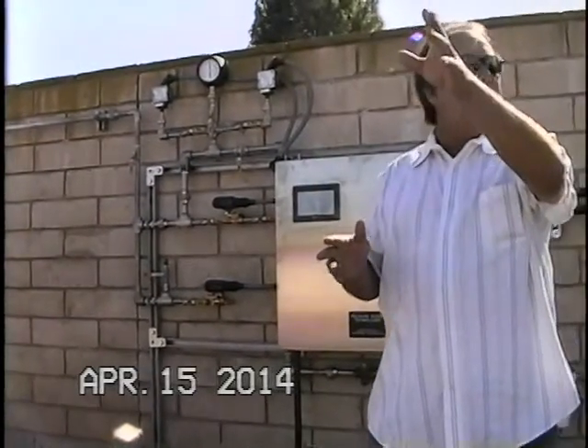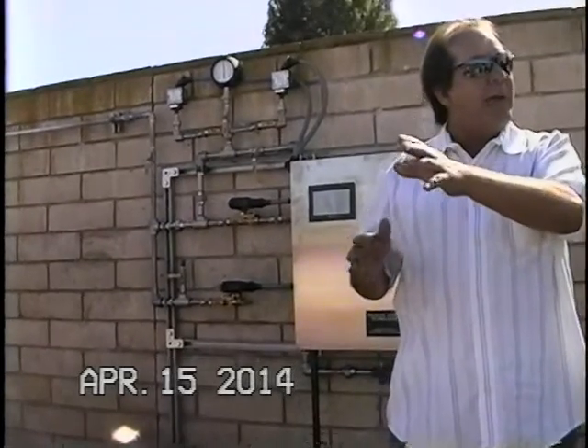In a surge tank, when the pump shuts off, we've got effluent flow, all this water leaving the pump station. Because of the velocity in the pipeline, this surge tank fills that void of the pumps, and eventually when that flow stops, it typically causes a pressure wave to come back at the pump station. All we do is dampen those effects with the surge tank.